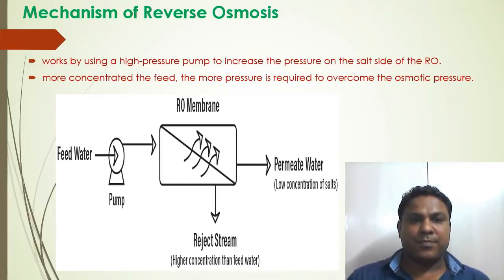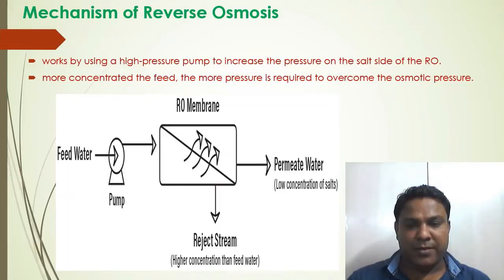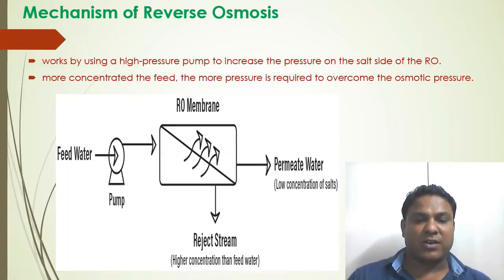Here the given diagram highlights the working of the reverse osmosis process. As the feed water enters the RO membrane under pressure, that is enough pressure to overcome osmotic pressure, the water molecules pass through the semi-permeable membrane and the salts and other contaminants are not allowed to pass and are discharged through the reject stream, also known as rejectant or concentrate, which goes to drain or can be fed back into the feed water supply in some circumstances to be recycled through the RO.